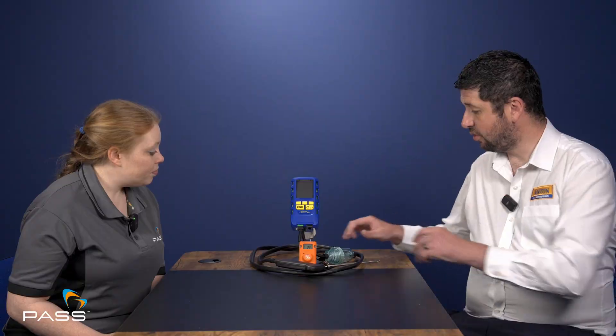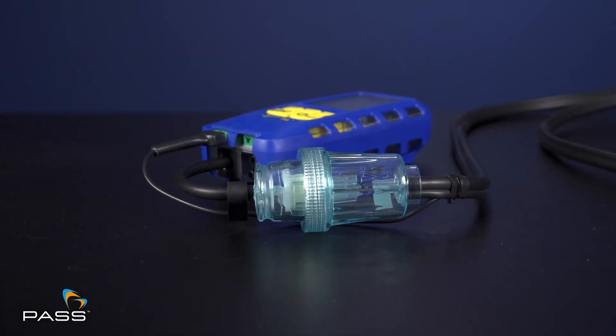One of the features that Anton is really proud of on the Sprint Pro series is the water stop technology. So we've got a water trap here — it's built on the outside of the analyser. We always say to engineers: don't leave them in vans overnight. If you leave water in your water trap overnight in the van, it's going to expand, crack, freeze. If it's situated inside the analyser, we're potentially going to damage the analyser. But ours is on the outside, so all you've got to do is replace the water trap. When it's full, the analyser is going to bleep and say your water trap's full — empty it and then carry on doing your flue gas reporting.